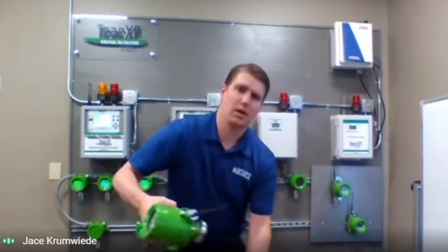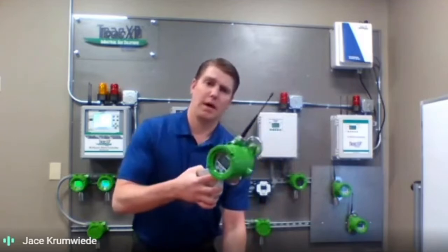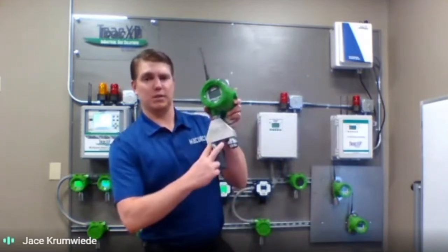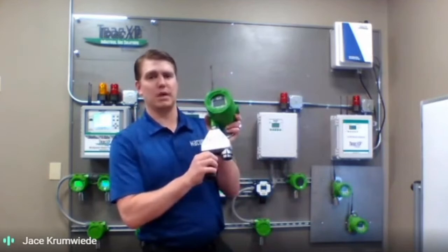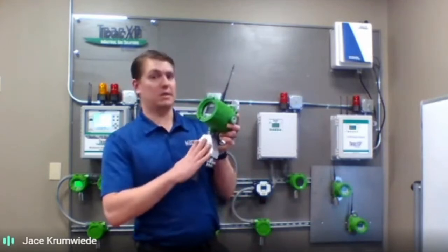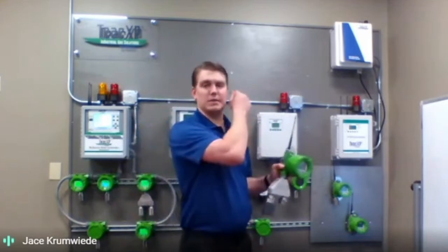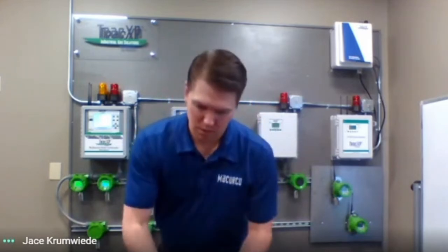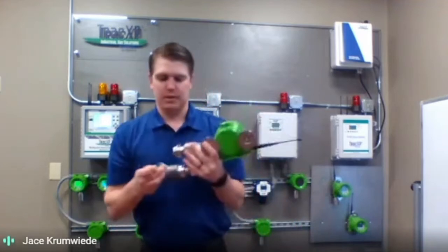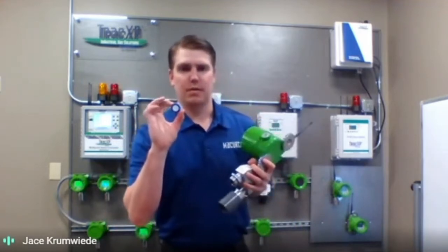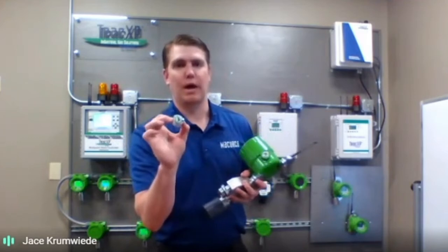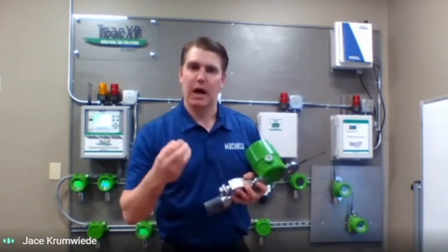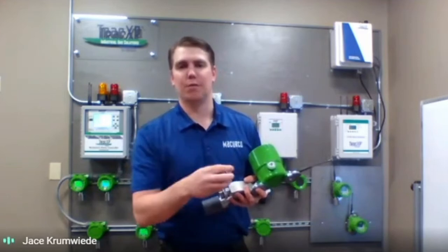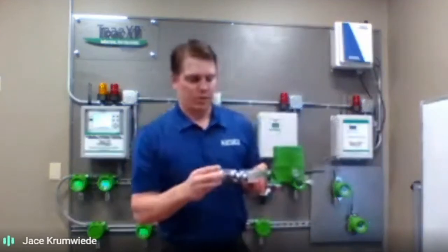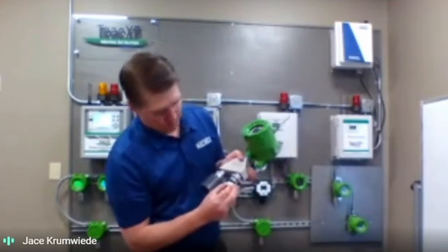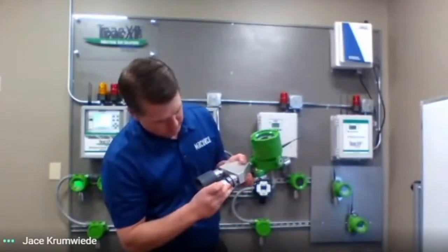So you could have, for example, this is, again, the polycarbonate. This one you have your aluminum enclosure. This one has a dual integral sensor, so you can have one sensor, two sensors, same gas, different gas, and this is going to communicate back in the same fashion. Very nice. How our sensors work is they are smart sensors, so you not only have that raw sensor, but you have a circuit board on there that's going to store the calibration and configuration information.